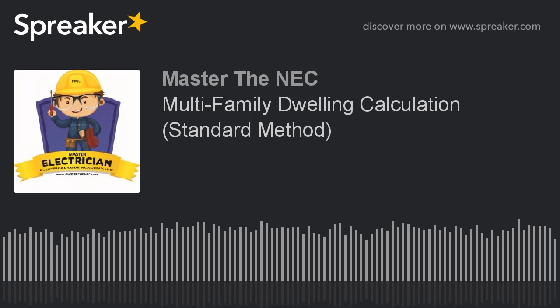Now, if you look at table 220.42, you'll see that it deals with the types of occupancies, and then it deals with the lighting load to which demand factors actually apply, or that portion of the value that we already calculated here. And of course, then you get your percentages and demand factors that you can apply. So let's look at it. We took the 54,000 plus the 54,000 plus the 27,000, which gave us 135,000 VA.